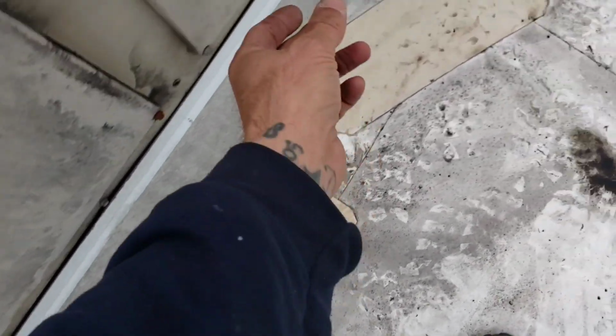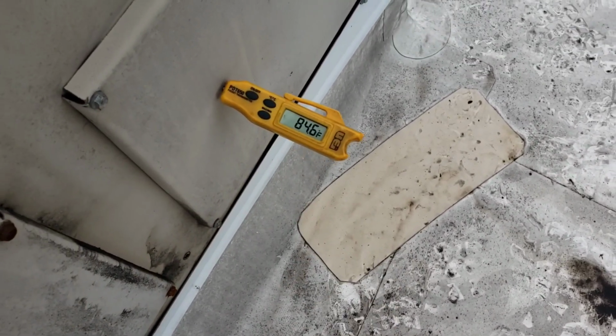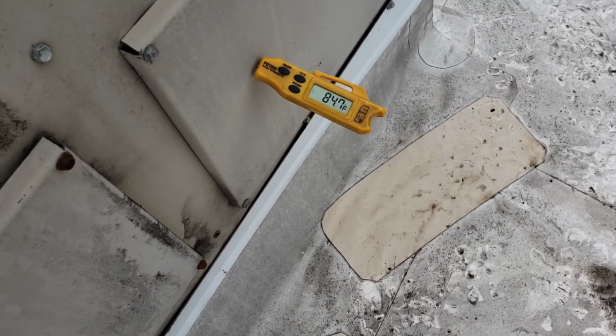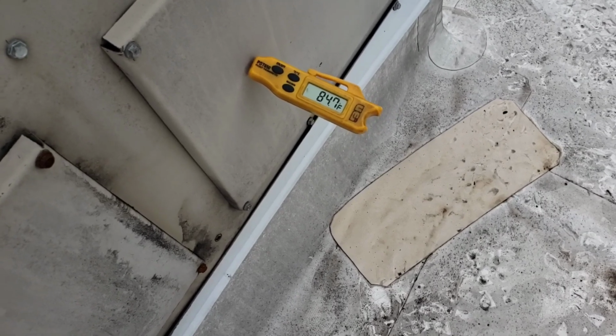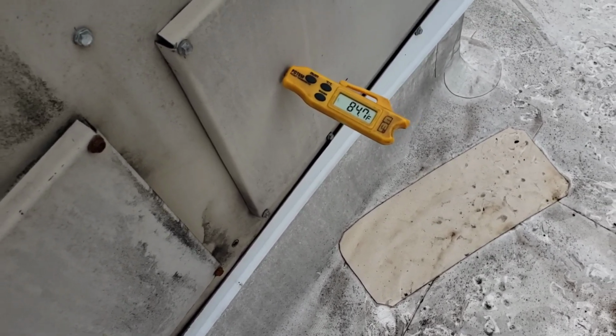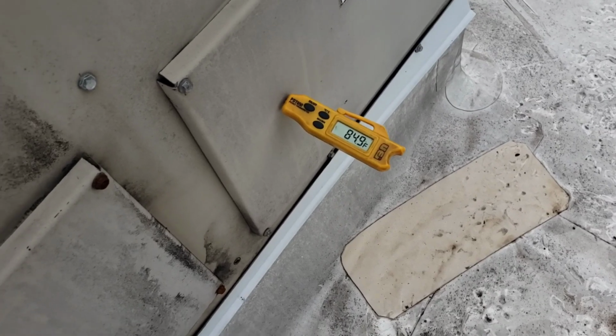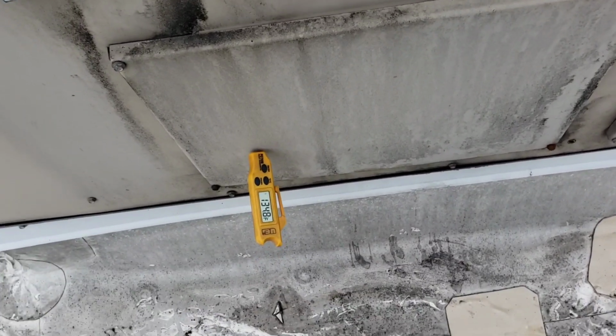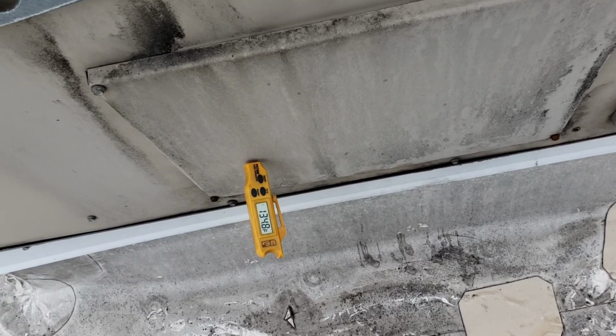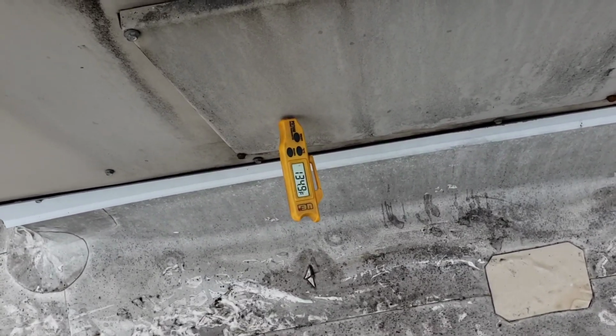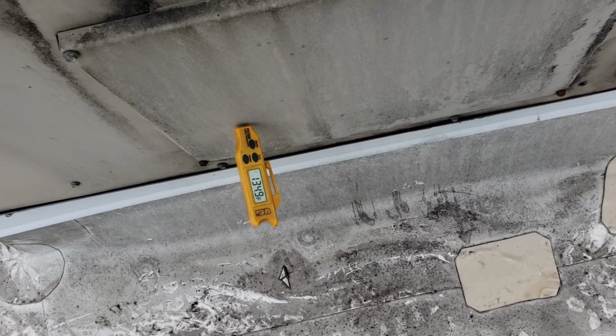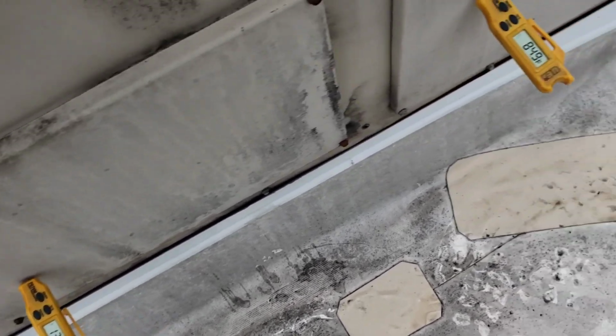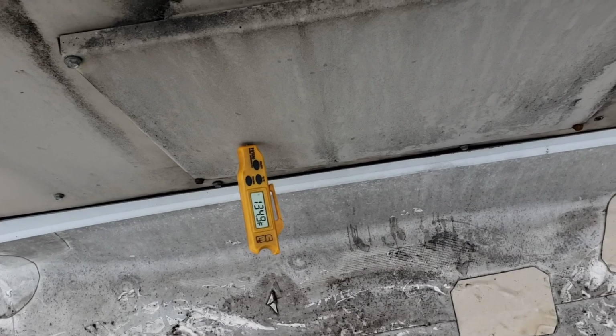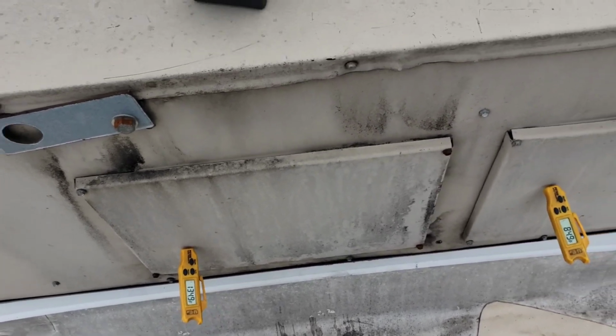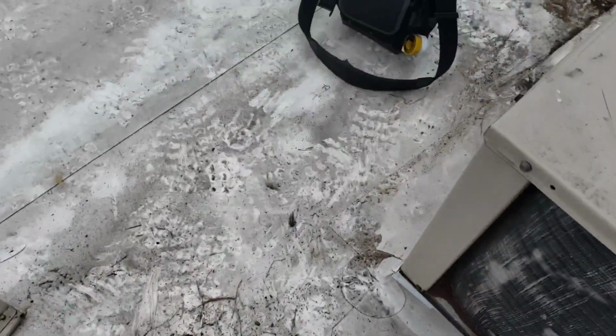Supply is 134, our return is about 84. It's obviously a pretty high return, but I'm not actually measuring it in any sort of ductwork. It'd be great if I could measure it from the diffuser downstairs, but I don't have access to the space we're heating. Really all I'm checking is my temperature rise, which on this unit is 30 to 60. So we got 84 to 134 - yeah, within tolerance. So far, no idea.